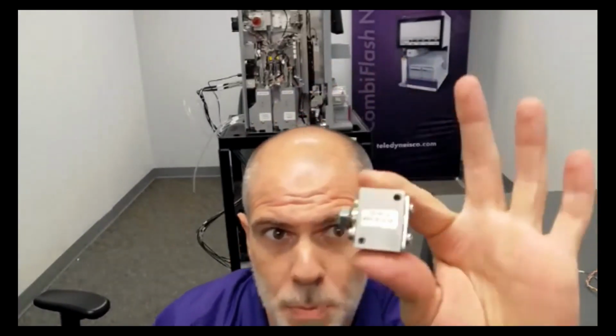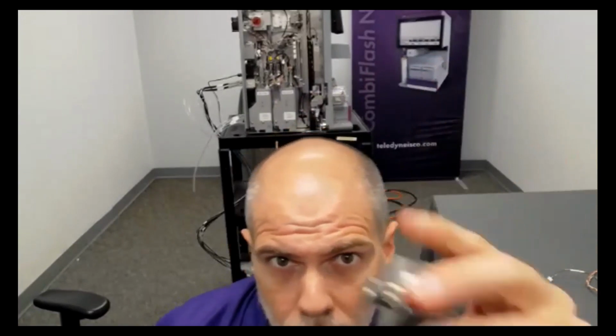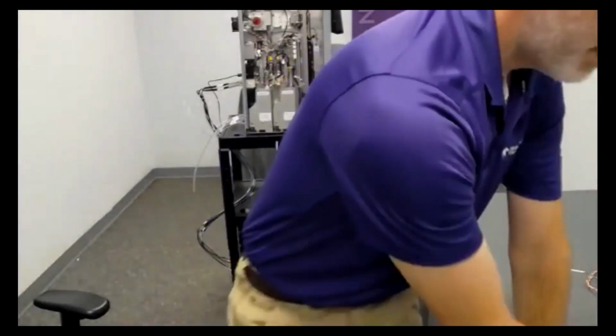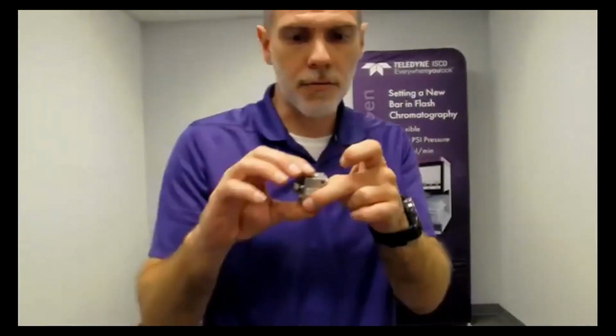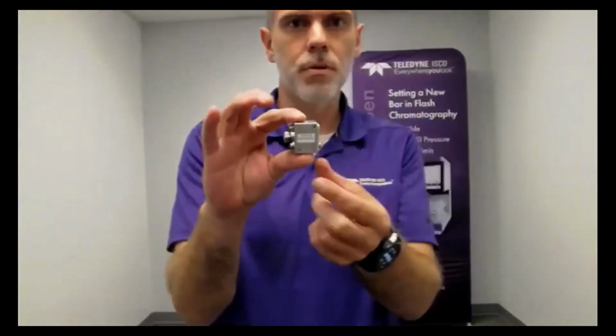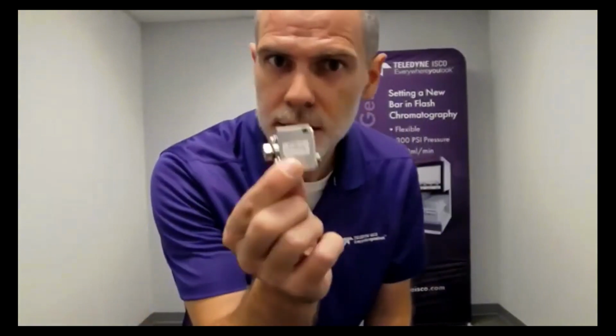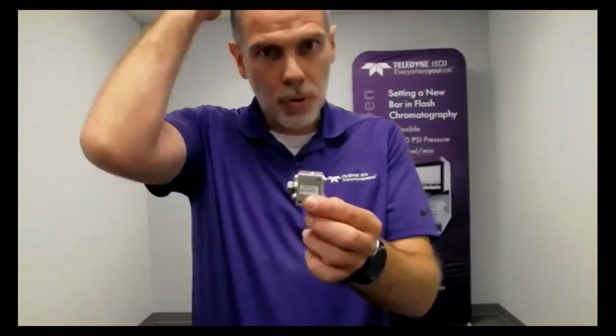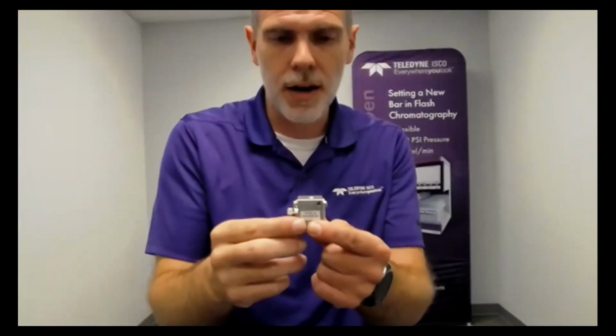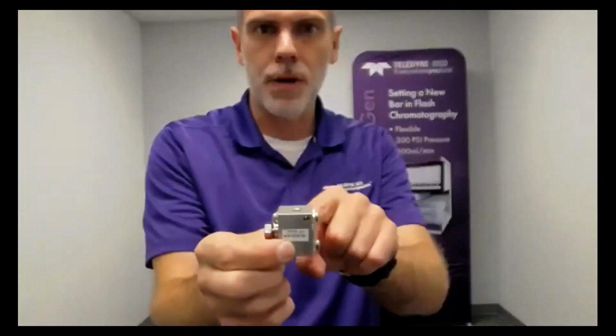And this is why I keep this one. It's an example of a bad flow cell. So what would happen if I installed this one back into the unit is I'd have perfect light level. The light would shine through, but you would never get any detection on this. And you'd be pulling your hair out if you have any. I don't. But you'd be pulling your hair out trying to figure out why you can't get detection. It's because you don't have a gap here.